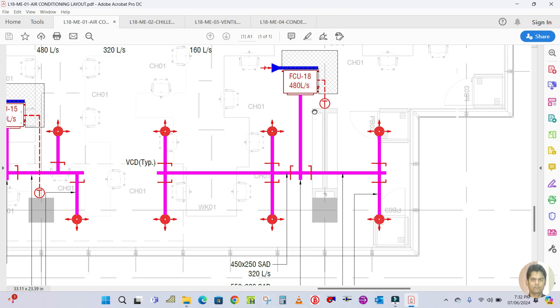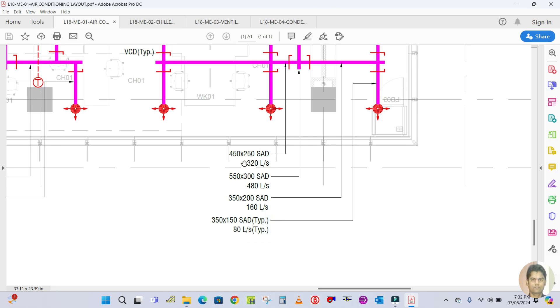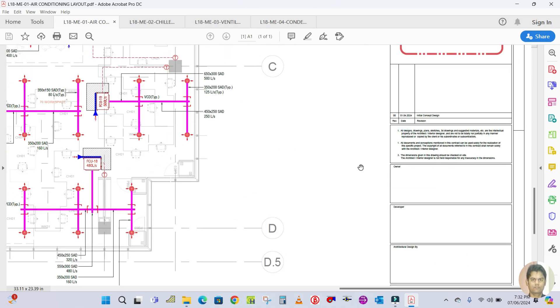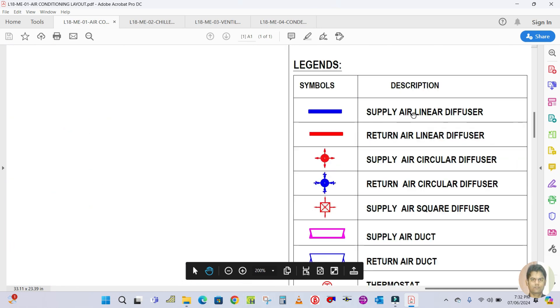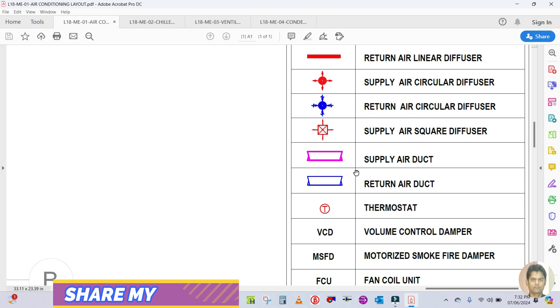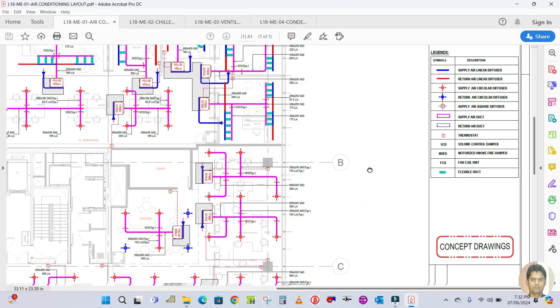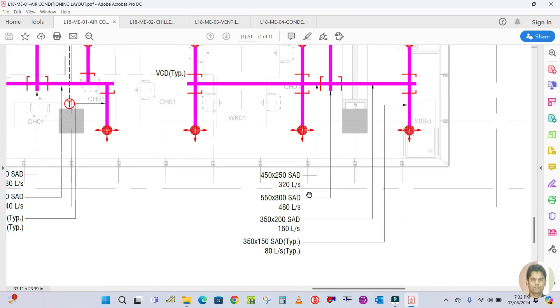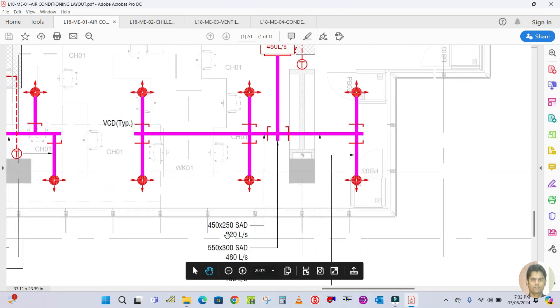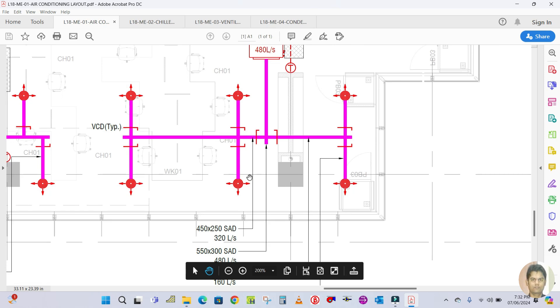This is the main duct. The size is given here — 450 by 250. 'SAD' stands for Supply Air Duct. The supply air duct is shown in magenta color in the legend. The main duct is 450 by 250 with 320 liters per second flowing on the left side.